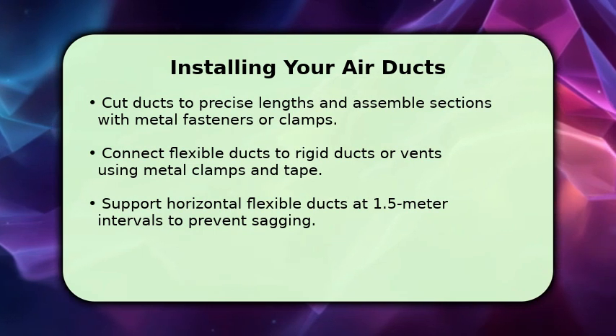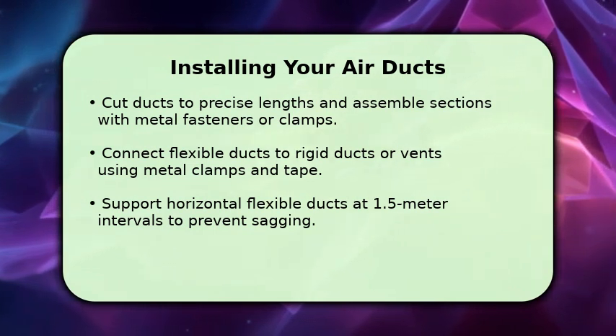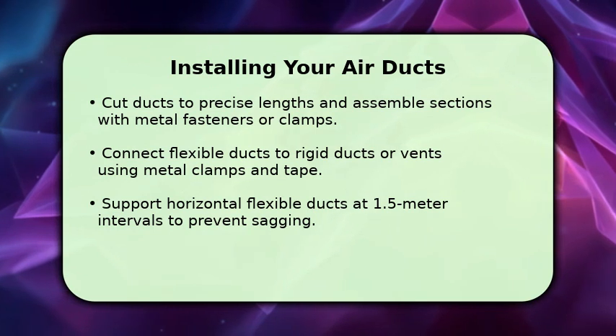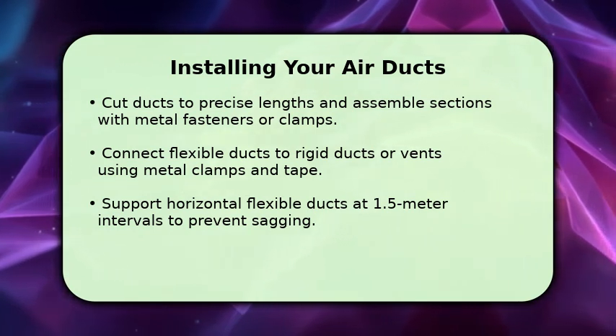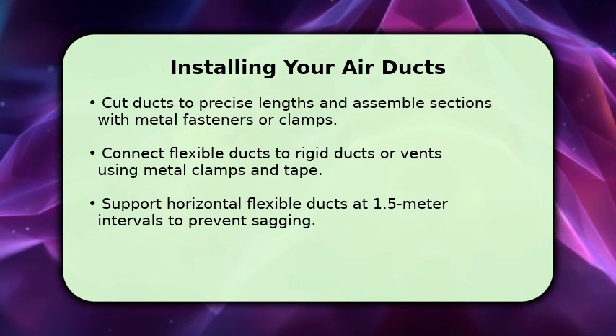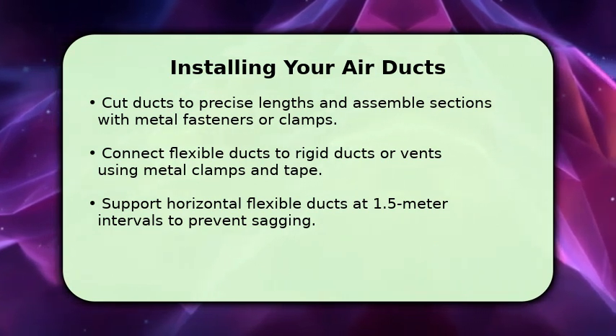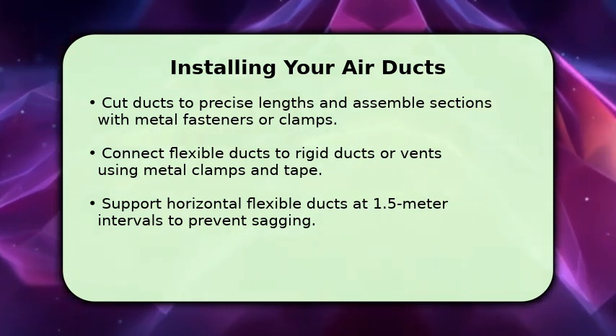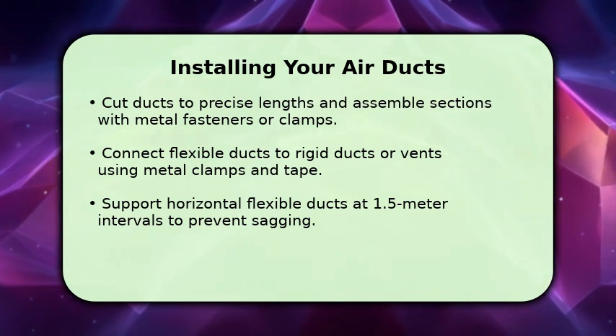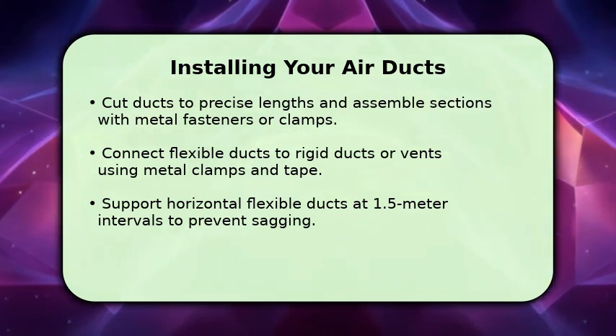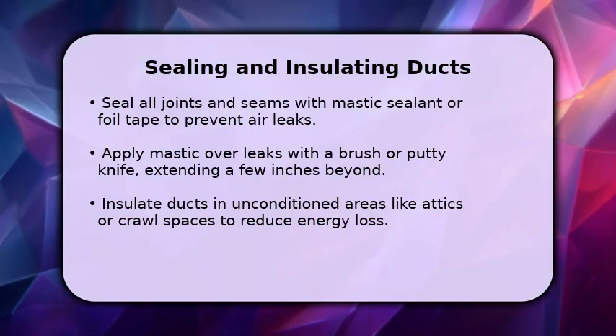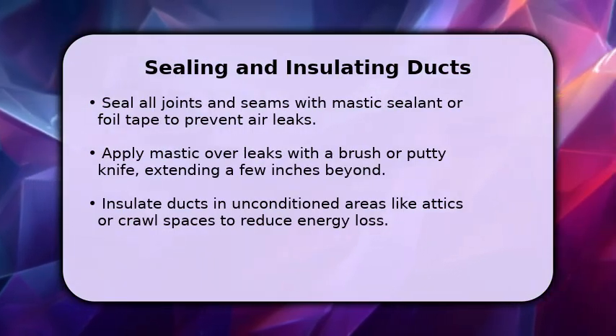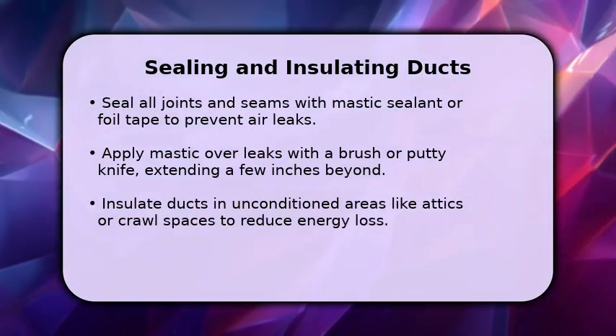When working with flexible ducts, connect them to rigid ducts or vents securely with metal clamps and specialized tape. It's also important to support horizontal flexible ducts at regular intervals, about 1.5 meters, to prevent any sagging and maintain optimal airflow. After installation, sealing and insulating your ducts is a critical step for efficiency.